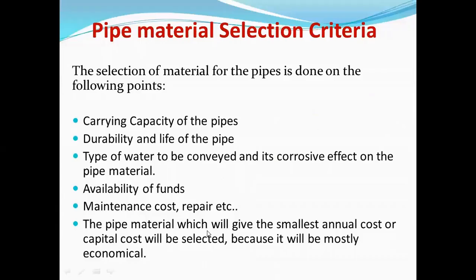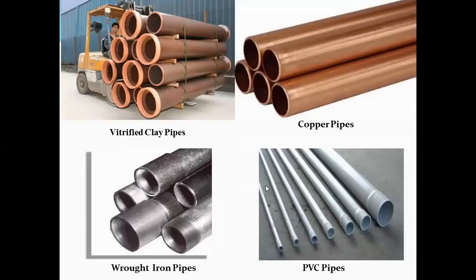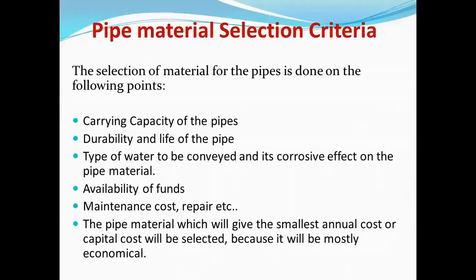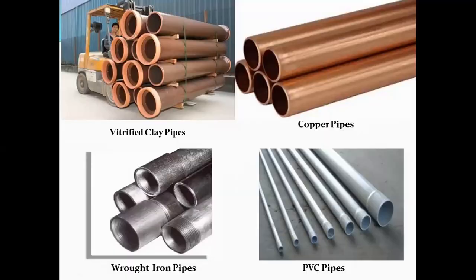Third is the type of water to be conveyed and its corrosive effect on the pipe material. If the water is somewhat corrosive in nature, then we should avoid using metallic pipes like copper, wrought iron, steel, or cast iron. Instead, we should prefer concrete pipe, vitrified clay pipe, or PVC pipe.